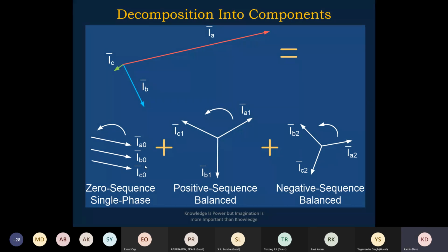But in a balanced phasor, the positive sequence is 98%, then negative sequence is 1.8%, and zero sequence is 0.2%, something like that. If it is an unbalanced phase to ground fault, let us say, then we will see positive sequence plus negative sequence plus zero sequence. The positive sequence is, for example, say 50%. The negative sequence is, for example, say 30%.